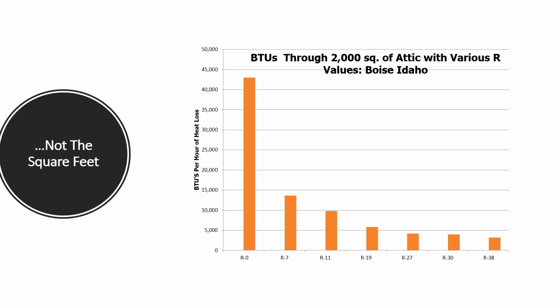And this is another way of looking at the same information. This is BTUs through a 2,000 square foot attic with various R values in Boise. Boy, you can see that at R0, you need a gas furnace just to handle the heat loss through the attic. By the time you get any insulation in the house at all, it starts to decrease rapidly. And by the time we get down to an R38, it's only about 3,500 BTUs of heat loss.